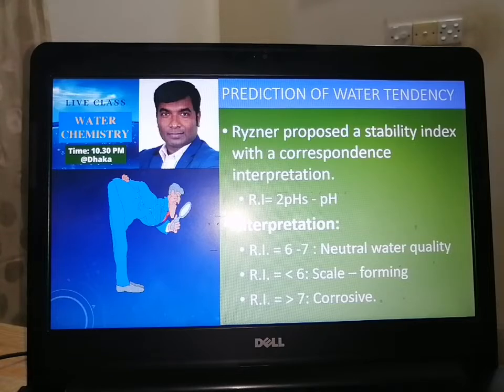Once you have the RSI prediction, we can understand how aggressive my water is - whether it will create corrosion or scale. Based on that we can design the treatment, design the plant machinery, and choose the metallurgy - which metal I should select, whether cast iron, galvanized iron, SS, or MS. In some cases we might have to select high grade materials, maybe titanium, for expensive heavy equipment.